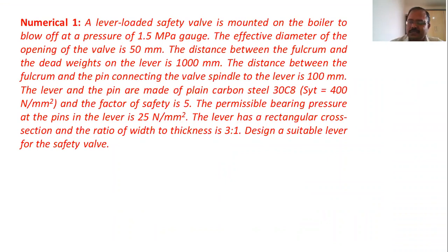Why is it necessary that the valve should blow at a certain pressure? Because each boiler is designed to be operated at a certain pressure only. If the pressure of the steam inside the boiler exceeds that limit, then there are chances of accidents, bursting of the boiler. So excess steam has to be relieved and the pressure inside the boiler should be brought below the safer values.